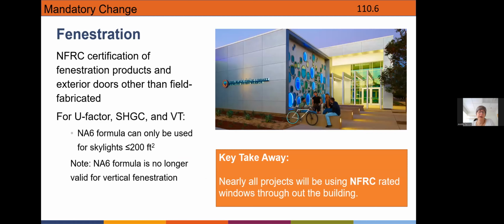Under the fenestration or windows, not a whole lot has changed. Really the big takeaway is that almost all the projects now will be using NFRC rated windows and fenestration throughout the building. So what's changed is that there was a formula that could be used to show that vertical fenestration or windows could comply with the standards, but that formula has been taken away, and the big push is to have everything NFRC rated.